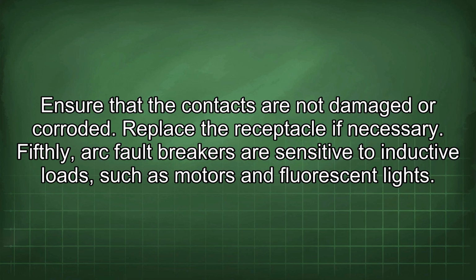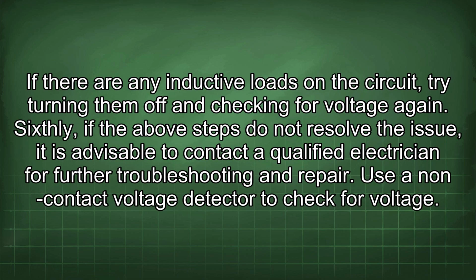Fifthly, arc fault breakers are sensitive to inductive loads such as motors and fluorescent lights. If there are any inductive loads on the circuit, try turning them off and checking for voltage again.